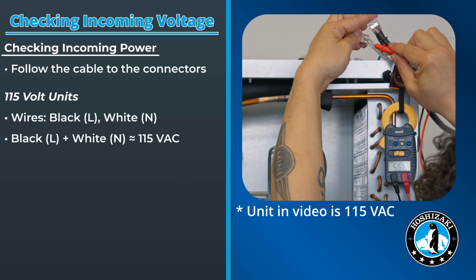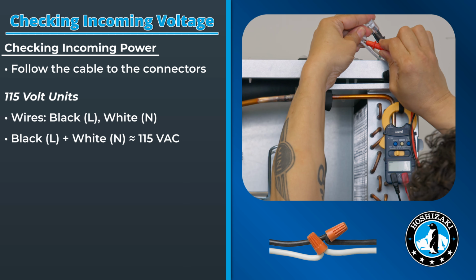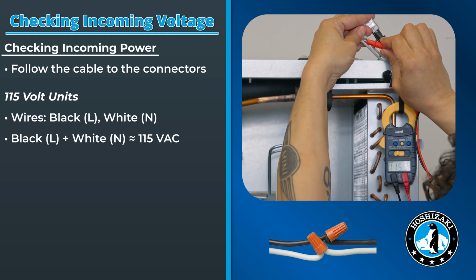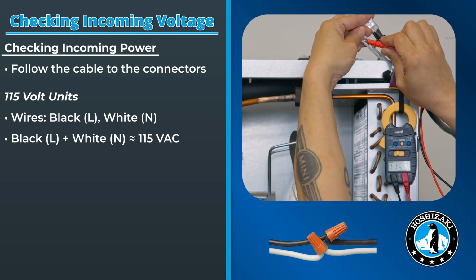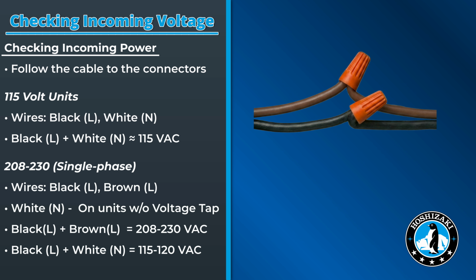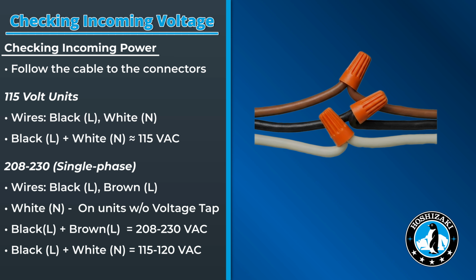For 115 volt units, check the voltage between the black line wire and the white neutral wire. The reading should be approximately 115 volts. For a 208/230 volt single phase unit, you will have a black and a brown line wire. Units without a voltage tap switch will also include a white neutral wire. Between the black and brown line wires, the voltage should read between 208/230 volts. Between the black line wire and the white neutral, the voltage should read approximately 115 to 120 volts.